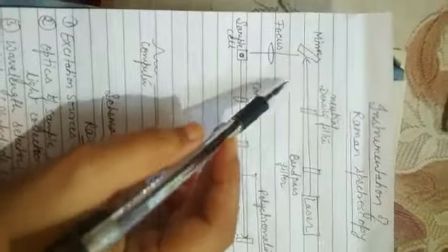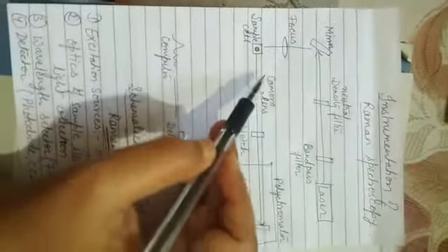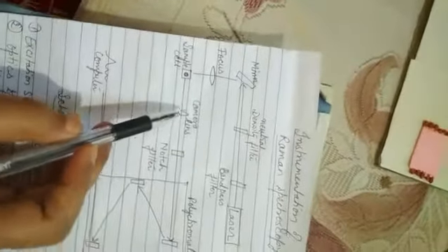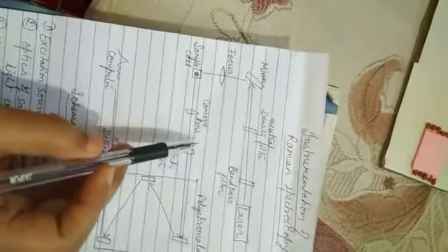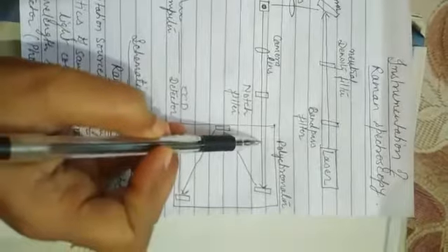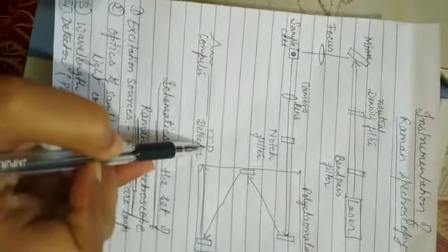Light from the irradiated spot is collimated by a lens and guided to an interference filter or spectrometer to get the Raman spectrum. Wavelengths near the laser line, corresponding to elastic Rayleigh scattering, are filtered out and the remaining collected light is dispersed on a detector.